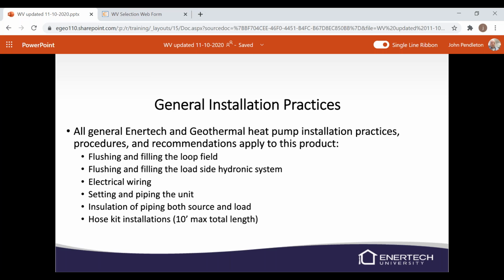Make sure we're insulating the load and the source piping, and we're still using the general installation practice of 10-foot max total length on our hose kit to our flow center. So the flow center needs to be about 5 feet from the unit. 5 foot there, 5 foot back equals 10 feet.